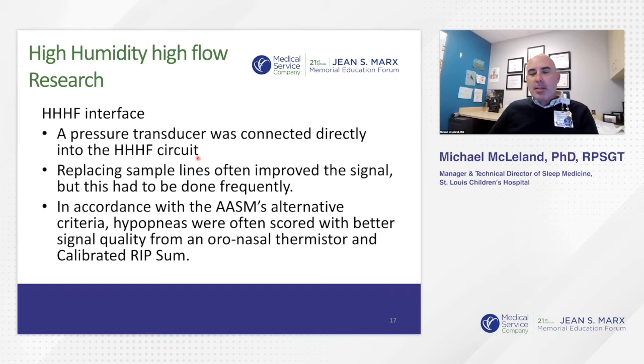Replacing the sample lines happened often because the high humidity would clog the sample lines, giving us a poor pressure flow. And that's kind of why we ended up adding in the thermistor.